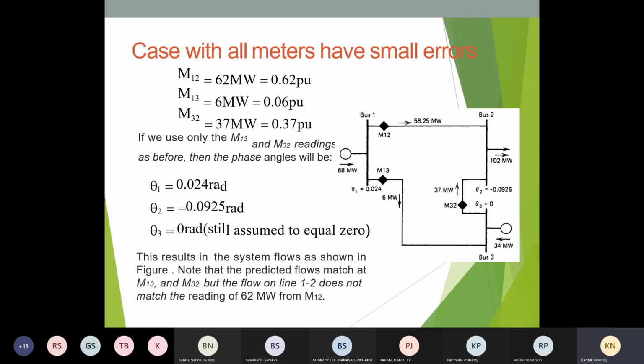These errors we will measure with the help of state estimation, and later in our network, we will consider state estimation with phasor measurement units, which measure the voltage and the change in angles directly and accurately. With the help of those V and thetas, the total load flows can be obtained in terms of a digital quantity before the fault or after the fault. There are many advantages of PMUs: if we know all those quantities, we can design the power system exactly, the stability of the power system is maintained, and we can tell exactly where the fault is observed, that is, the fault diagnosis. Many advantages come with state estimation using PMUs. That's the main intention of this whole presentation.